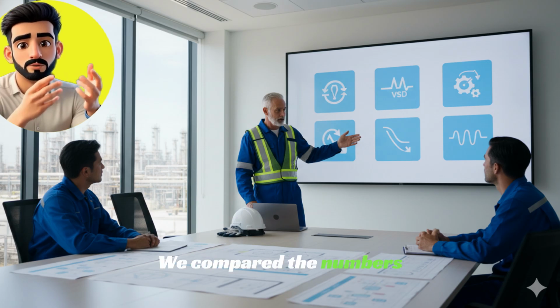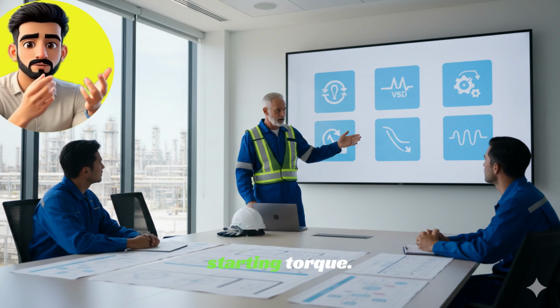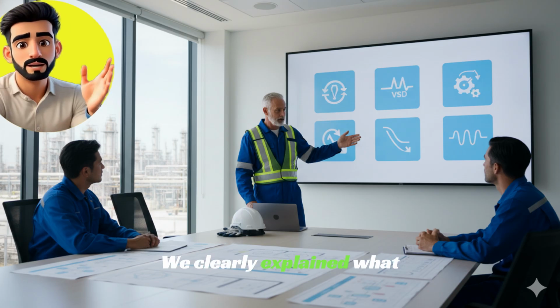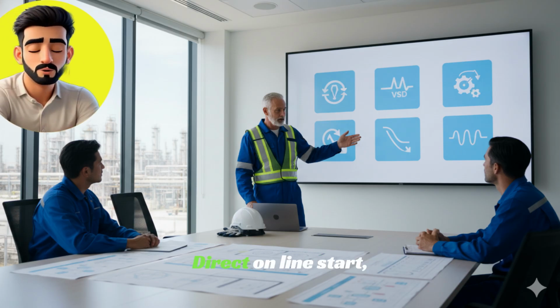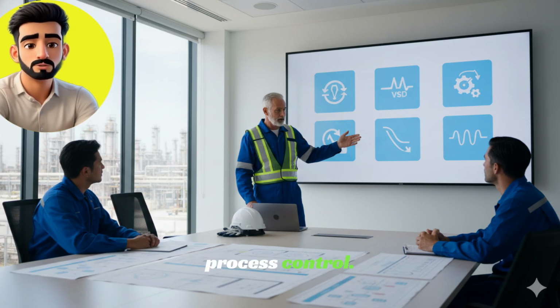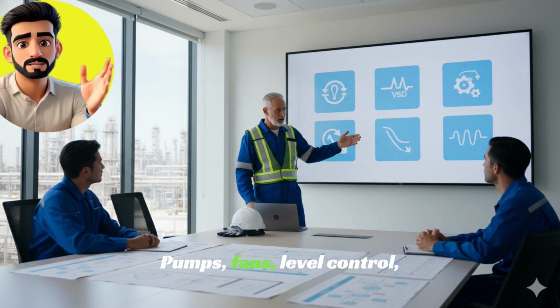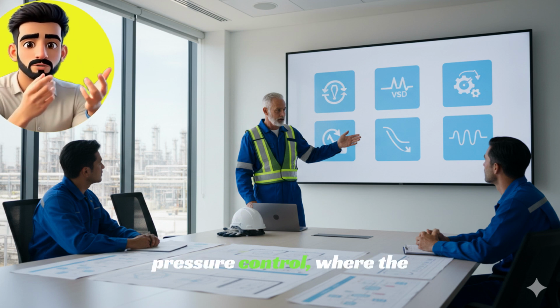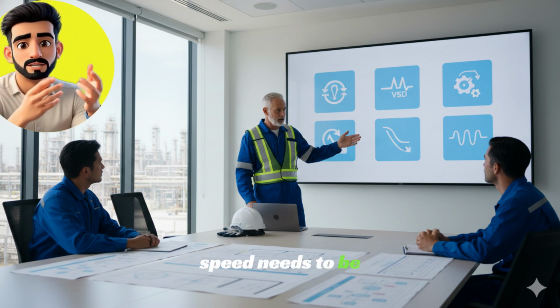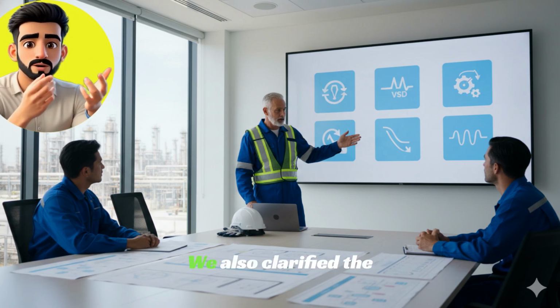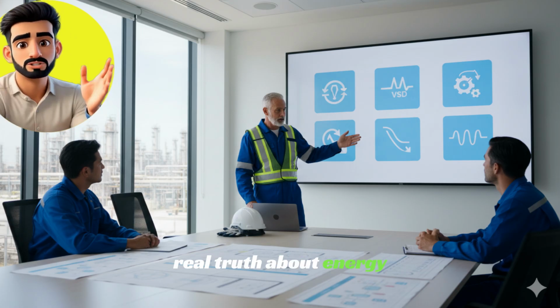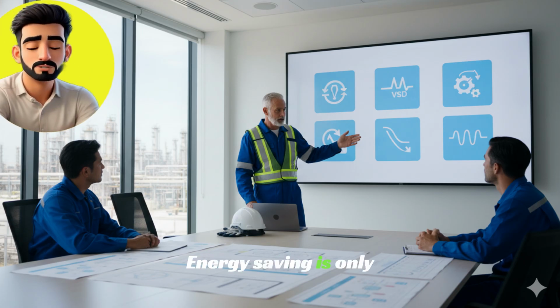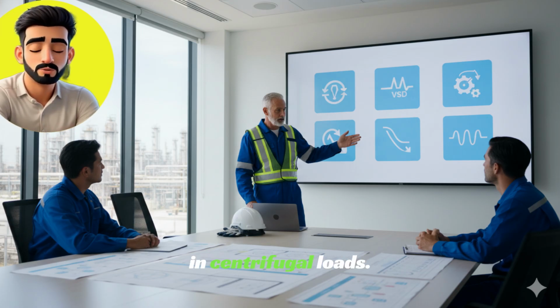We compared the numbers of starting current and starting torque. We clearly explained what the difference is between direct online start, soft starter start, and VSD start. We moved on to process control, pumps, fans, level control, pressure control. Where the speed needs to be continuously adjusted, VSD is the king there. We also clarified the real truth about energy saving. Energy saving is only a real game changer in centrifugal loads.